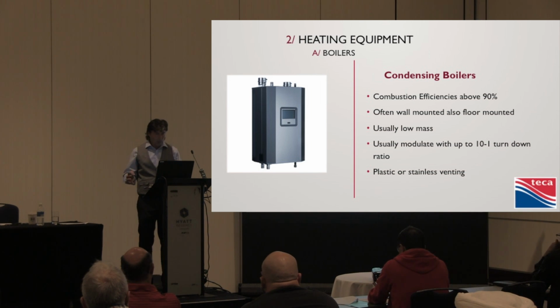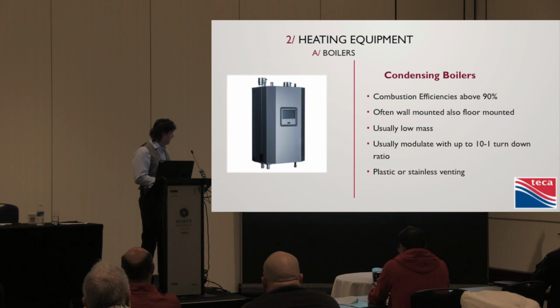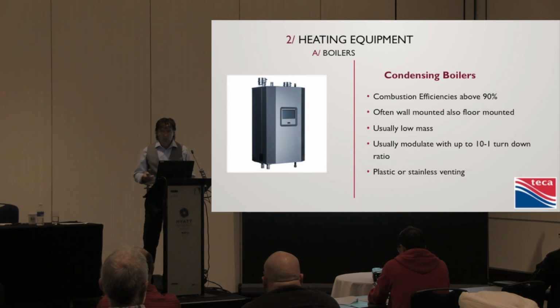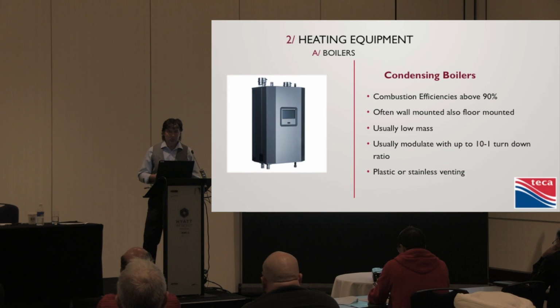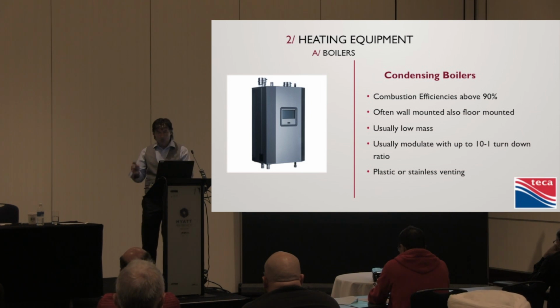That's a good step. Is it the best thing in the world? Well, I don't think so. Actually, I would buy this boiler more because of that turn-down ratio. When I buy that boiler, what am I going to size it for? I'm going to size it for the coolest day. The code's going to tell me to do that, especially CSA F280. So you've got to size your appliance, and you don't want to oversize it. You want to size it for the job.